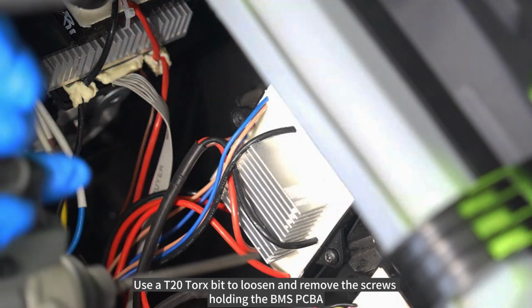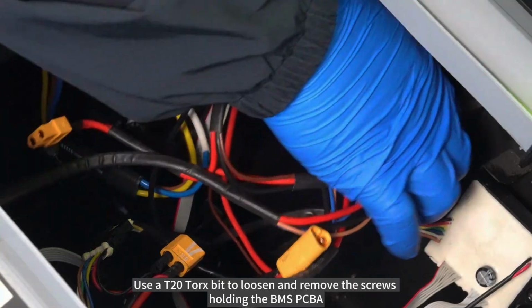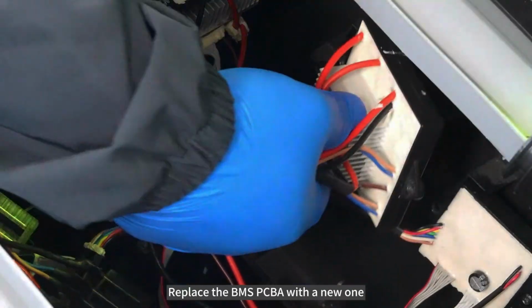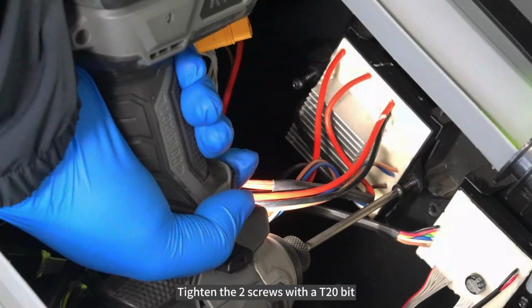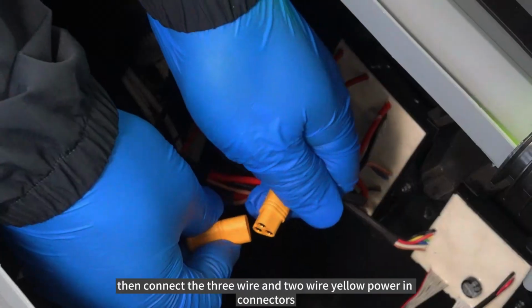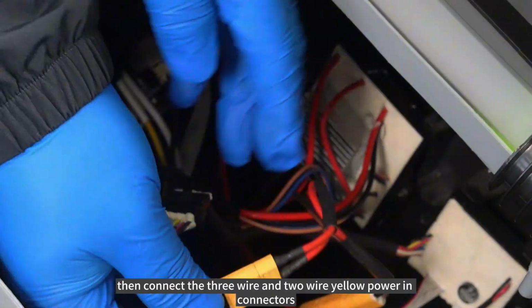Use a T20 Torx bit to loosen and remove the screws holding the BMS PCBA. Replace the BMS PCBA with a new one. Tighten the 2 screws with a T20 bit, then connect the 3-wire and 2-wire yellow power in connectors.